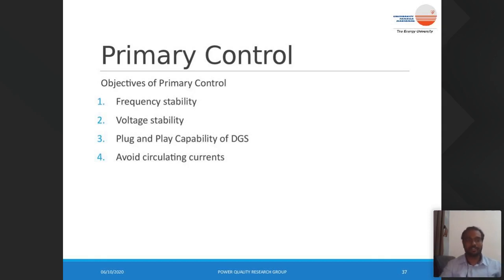The objective of primary control is to stabilize the frequency and voltage, and it is mandatory because once the frequency violation occurs, then the instability of the microgrid is imminent. It's very hard to restore the frequency once it has gone below a certain level, and all the inverters will lose synchronism. And voltage stability also matters because below a certain voltage, all the inverters pull out of synchronism, and it will lead to a blackout of the microgrid.